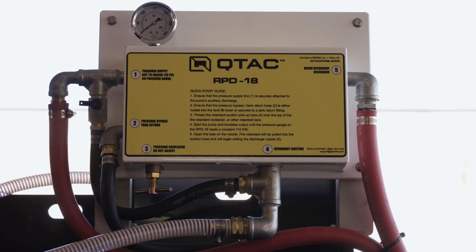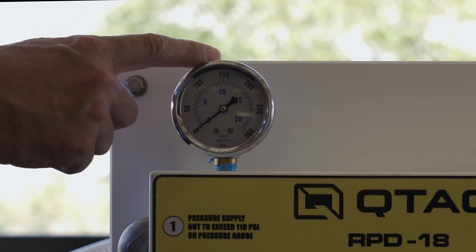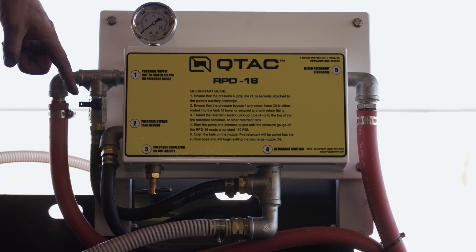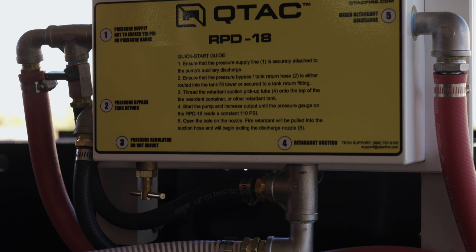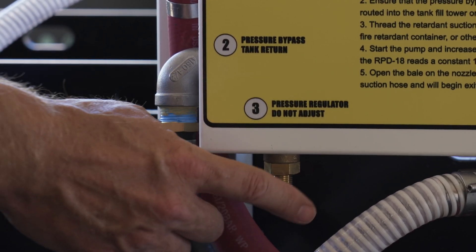The QTAC RPD18 is a device designed to proportion Phos-Chek LC-95FX to 18%, or within the acceptable range. On the top of the RPD18, you'll find a pressure gauge. Below that is the water pressure supply line. There's a pressure bypass valve that returns water to the tank. On the bottom is a pressure regulator, which should not be adjusted.